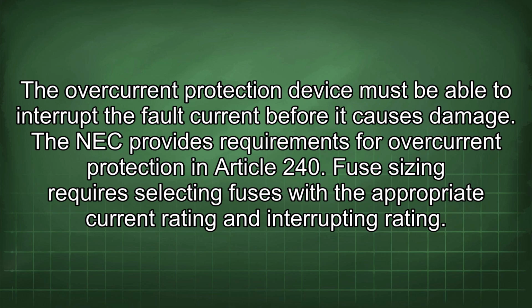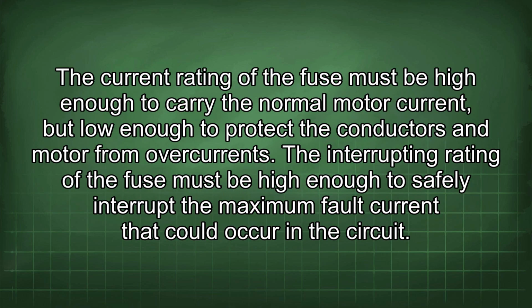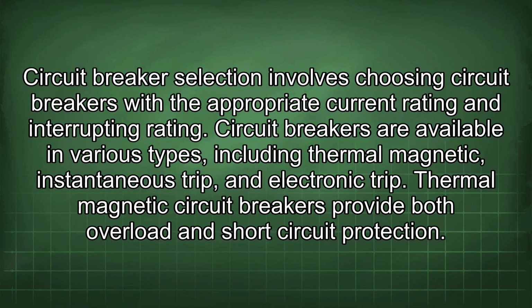Fuse sizing requires selecting fuses with the appropriate current rating and interrupting rating. The current rating of the fuse must be high enough to carry the normal motor current, but low enough to protect the conductors and motor from overcurrents. The interrupting rating of the fuse must be high enough to safely interrupt the maximum fault current that could occur in the circuit. Circuit breaker selection involves choosing circuit breakers with the appropriate current rating and interrupting rating.